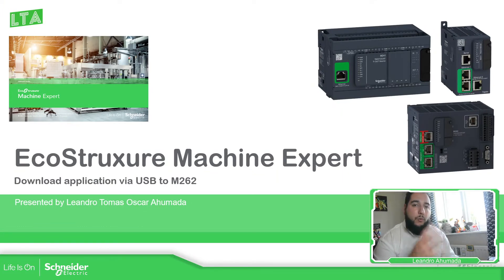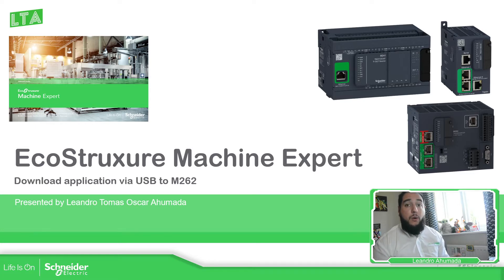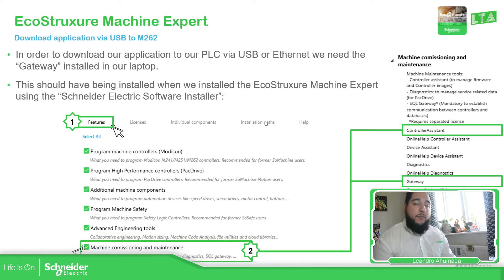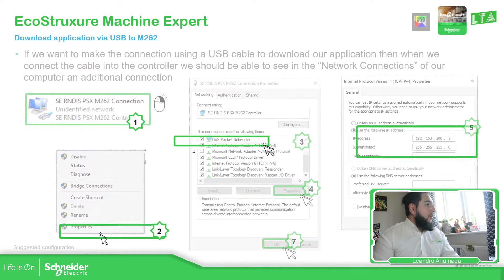The first thing that we need in order to download an application to the M262 is to have the Machine Expert. To have the Machine Expert, we must download from our website the Schneider Electric Software Installer. Once we select the Software Installer, it is important that we must select on the features this one — Machine Commissioning and Maintenance — because this one has the tools that allow us to have the drivers and also the gateway that allows us to connect with the device. So that's the important thing.